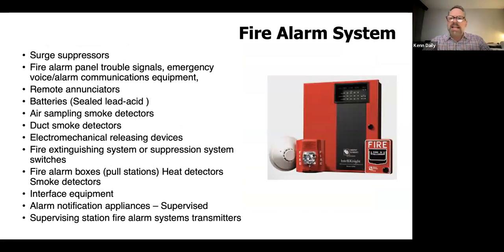And again, it has air sampling, it has fire or heat detectors. It can have smoke detectors, horns and strobes and pull stations. And then, of course, you have a lot of communication pieces and parts. So all of these are visually inspected on a semi-annual basis. And then each one of these items is going to be functionally tested on an annual basis.